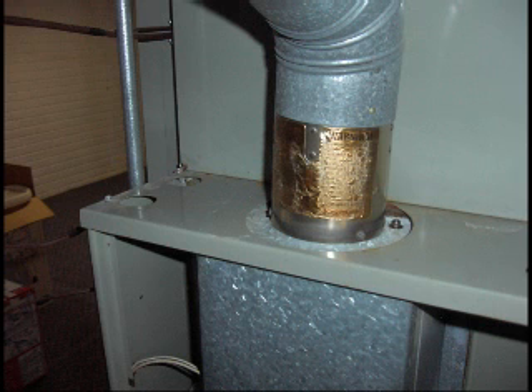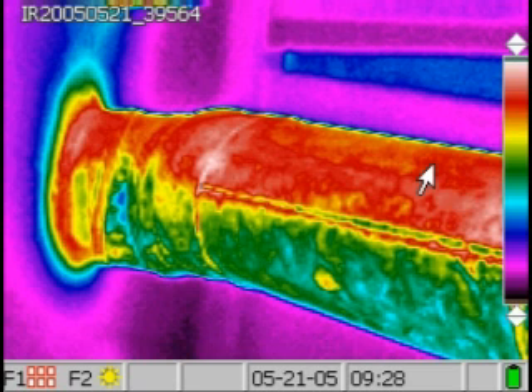And you might even have a heat transfer problem. This is where you're overheating the heat exchanger and you're creating high carbon monoxide. You can't find out any of this without a combustion analysis. And like I said, 90% of the heating contractors do not perform these.